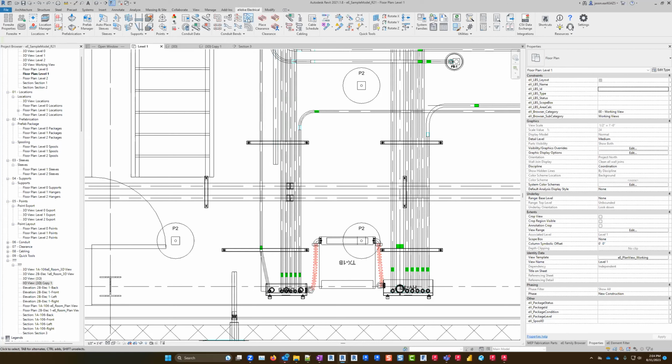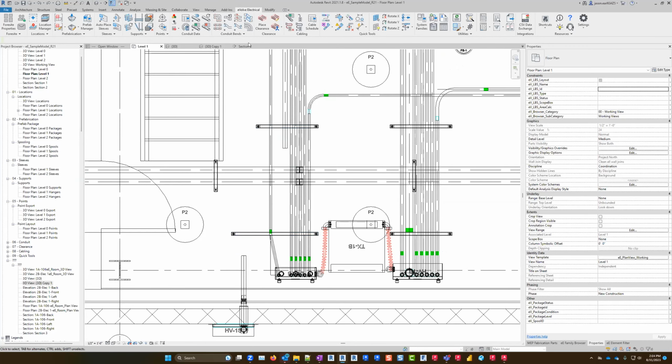The other function that it has is the shift function. Many of our features have shift functions. You'll know because it's got an asterisk on the icon, and when you hold shift, it will do something different. In the case of Smart Bend Multi-Trim, what that's going to do is allow you to replace a native Revit offset or kick with an Evolve Smart Bend. So if you've got somebody on your team, or if you just prefer to draw conduit the old-fashioned way, you can still do that and very quickly convert those into Smart Bends. Let's look at a couple examples now.